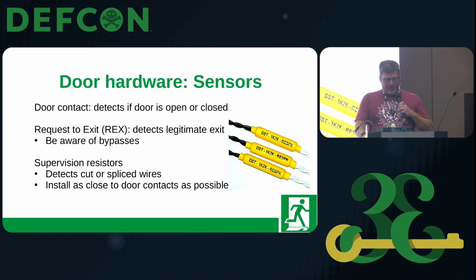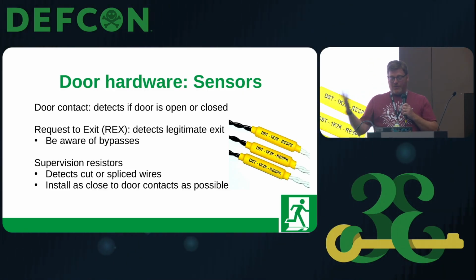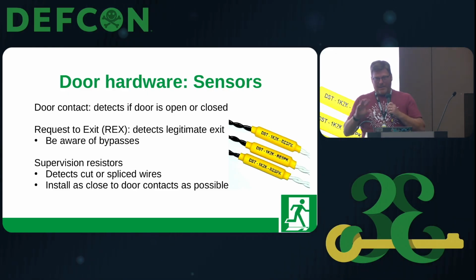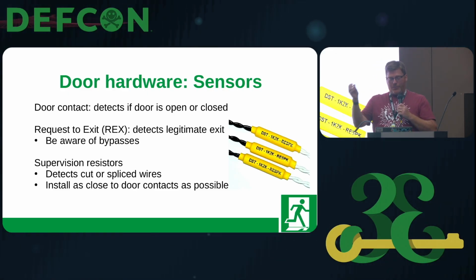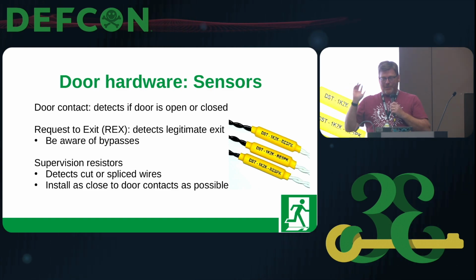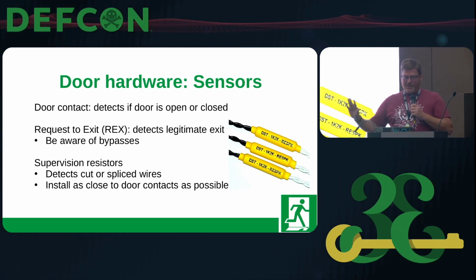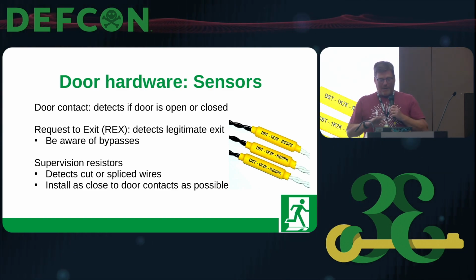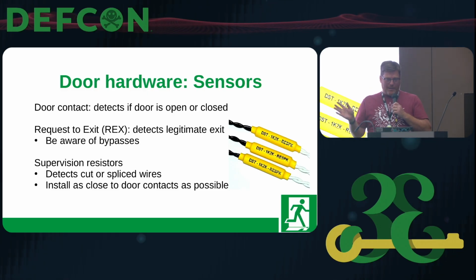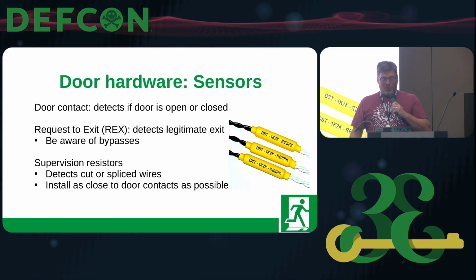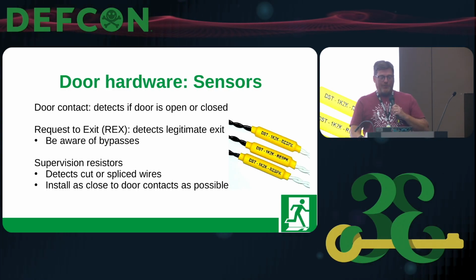So those door sensors I was talking about: a door contact detects if the door is open or closed, and the REX, or request to exit, is again a micro switch or a motion detector or even a push button that says this door is about to open legitimately from the inside with somebody leaving. There are bypasses for all of those, so think about that when you're deciding what you want to do. What is almost never done are supervision resistors.